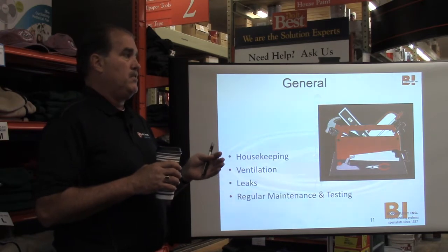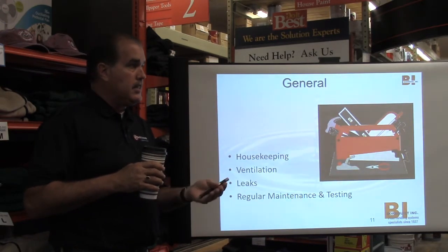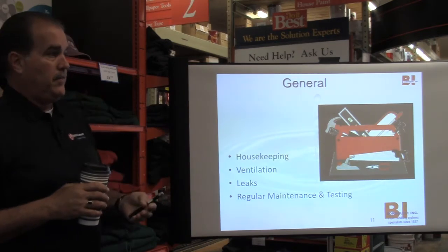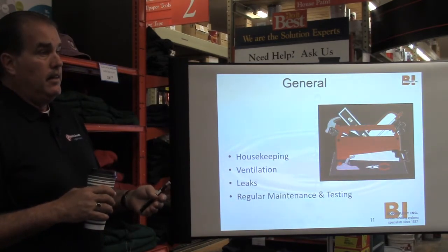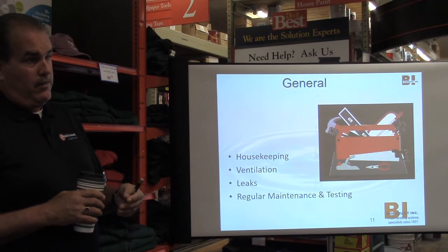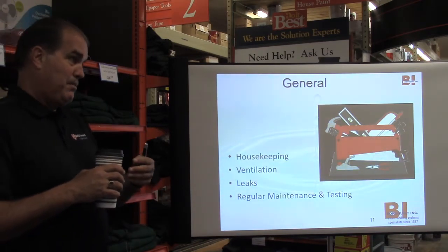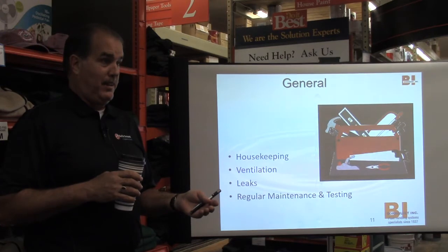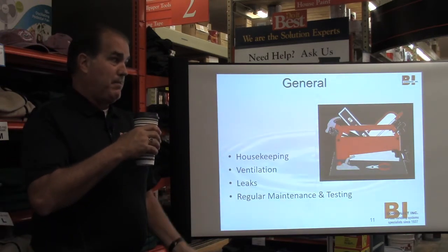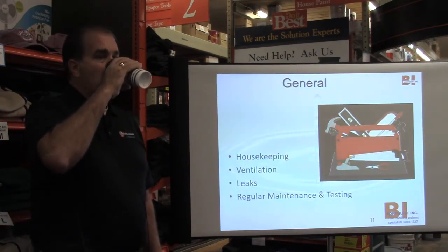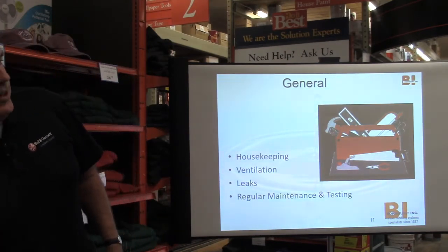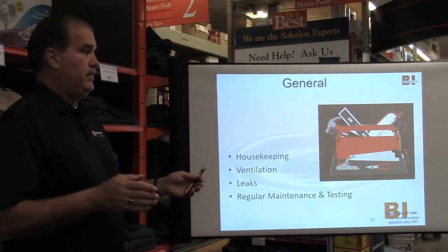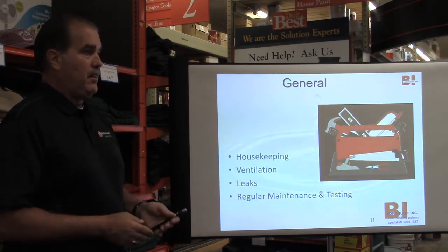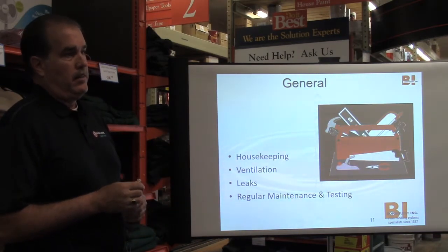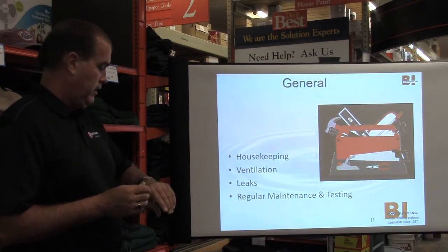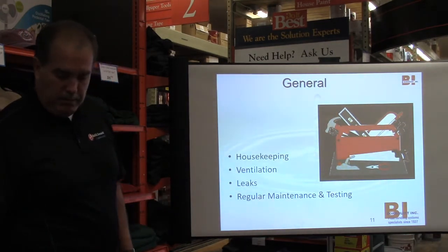Because usually those additives are going to be something used for cleansing or removing calcium and stuff like that, which is a good thing if you have a newer system. If you have an older system, what can happen is now you remove that calcium, and that's about the only thing holding those pipes together, and guess what? You got leaks popping out all over the place. So it's a double-edged sword. I say water treatment is good, but you got to be careful on really old systems because you can actually get yourself into more trouble than it's worth. So be careful of that.